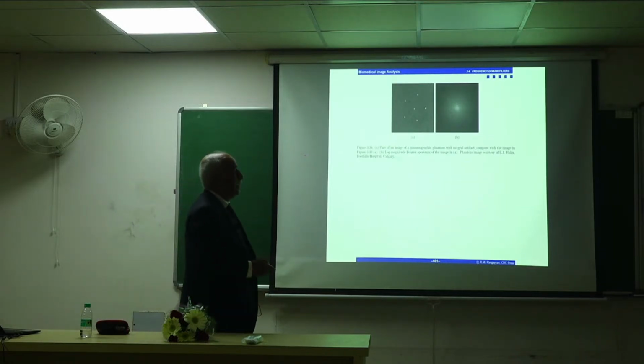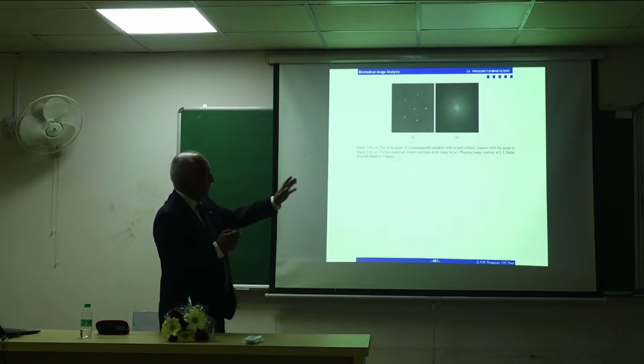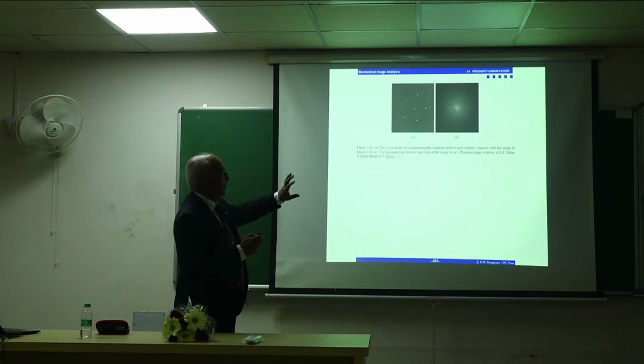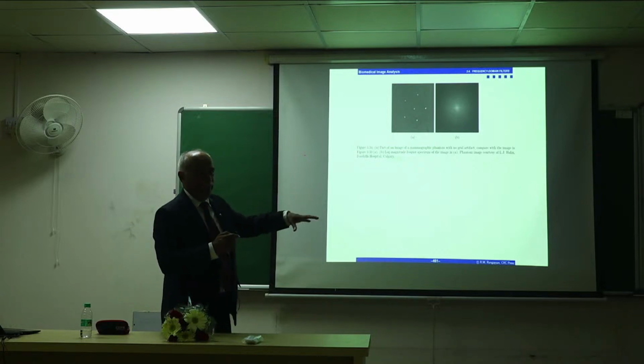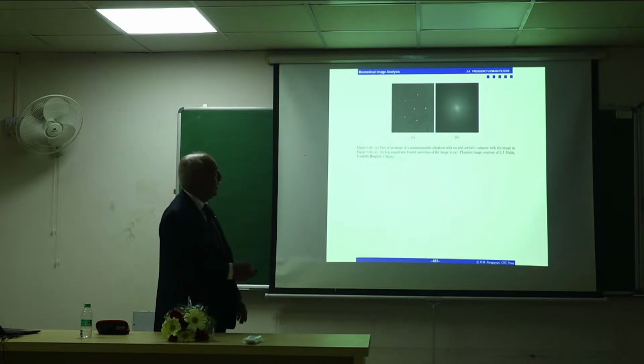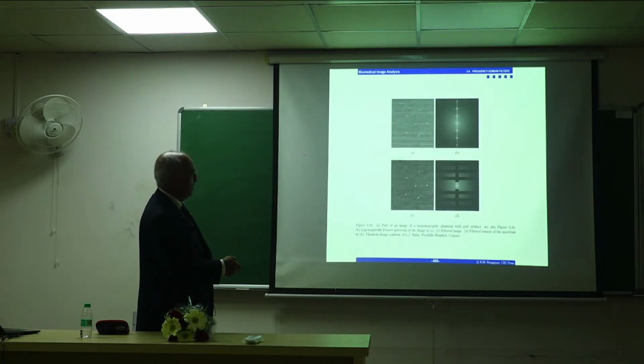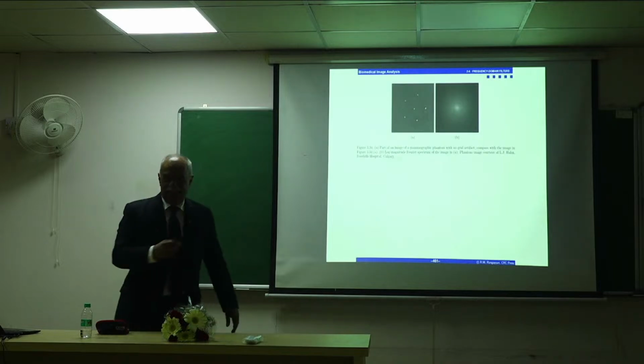This is the original image if the grid had worked properly. Now, you wouldn't take such images with and without grid movement with patients, of course. You can't do that twice. So with the phantom, we could do such a thing. So this is how it should have been, and its spectrum. The filtered one is not like that.